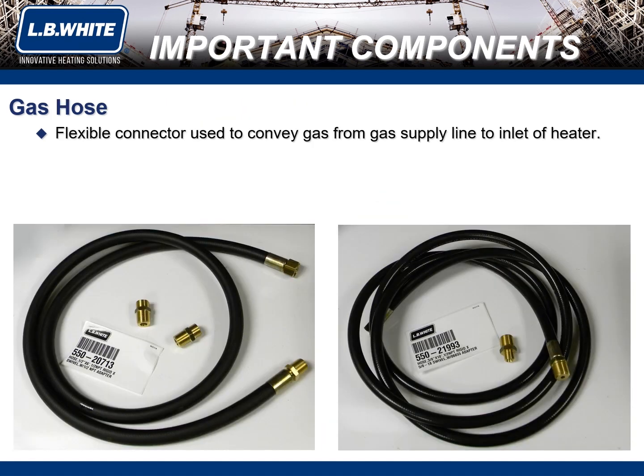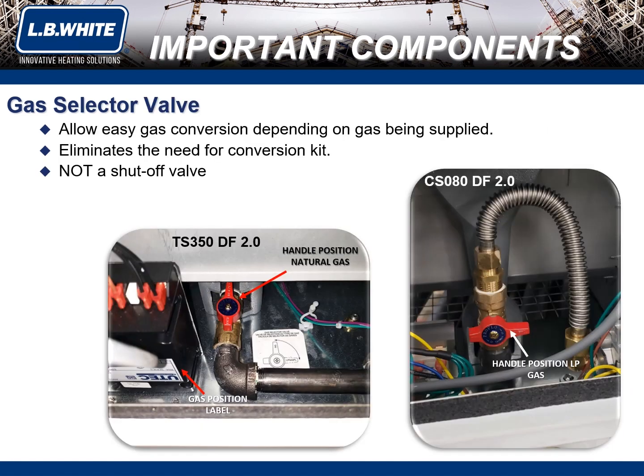A gas hose is a flexible connector used to convey gas from the gas supply line to the inlet of the heater. A gas selector valve allows easy gas conversion depending on the gas being supplied in a dual fuel heater. It conveniently eliminates the need for a gas conversion kit. One thing to keep in mind is the gas selector valve is not a shutoff valve. On our heaters, when the knob is in the horizontal position, it is ready for LP gas, and when it is in the vertical position, it is ready for natural gas.